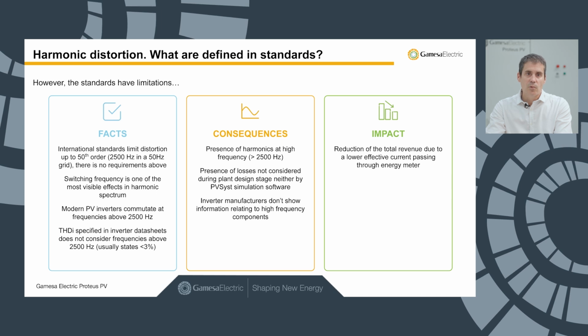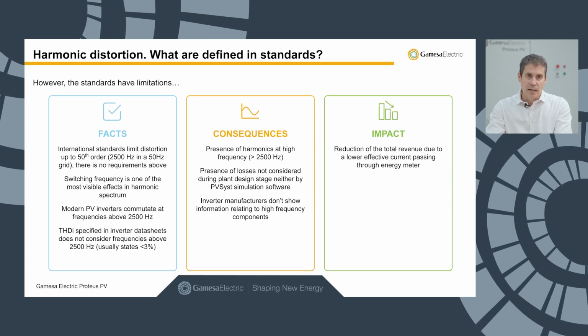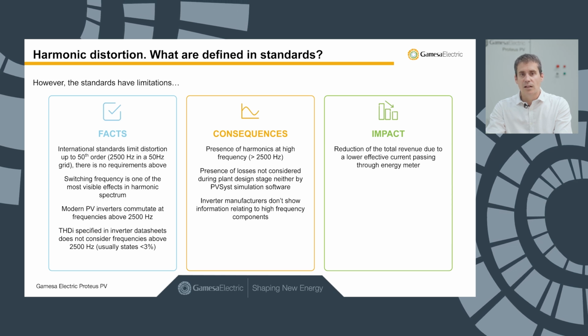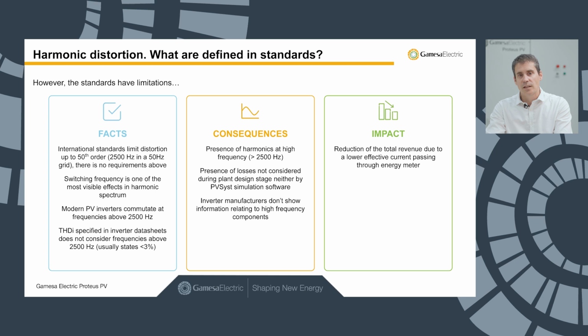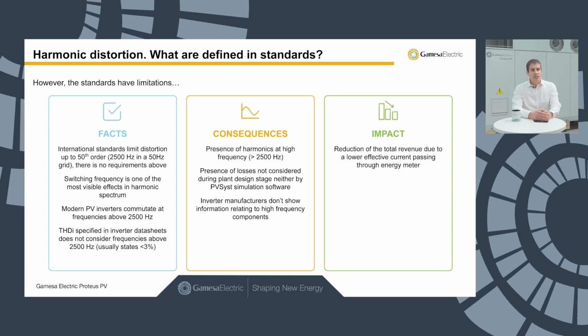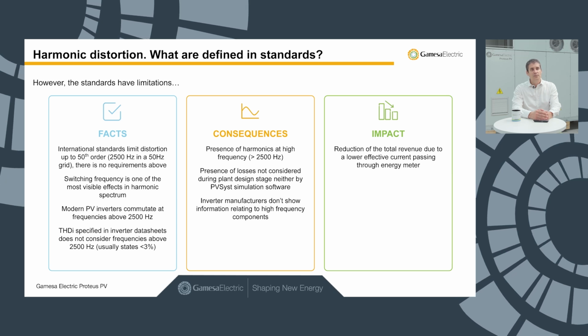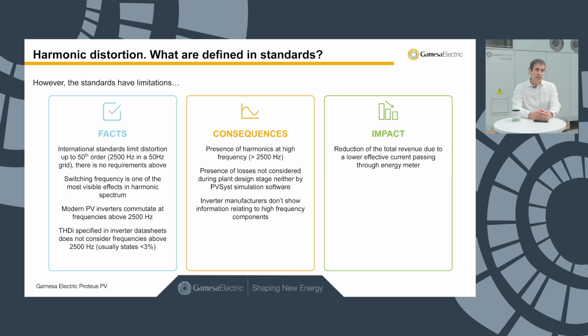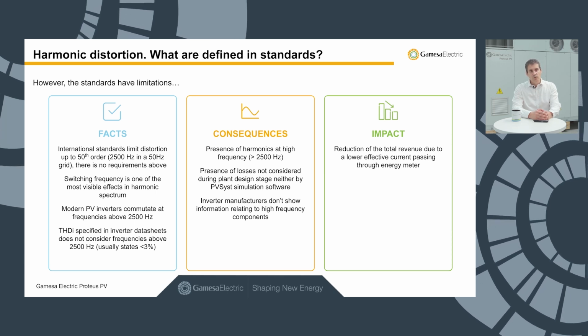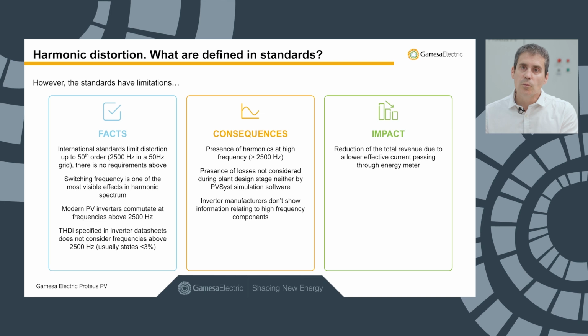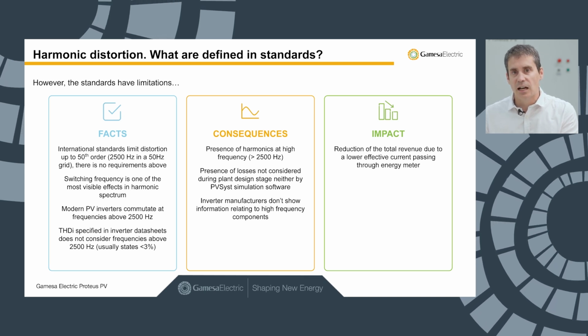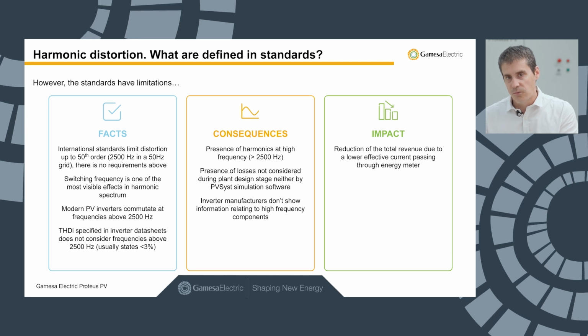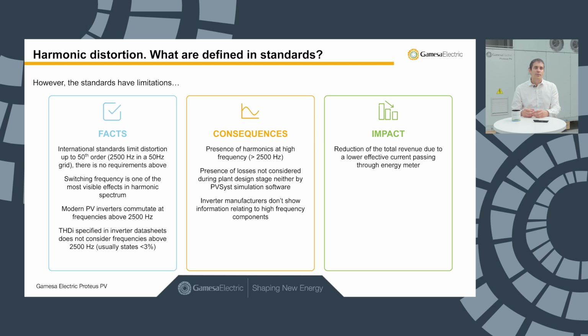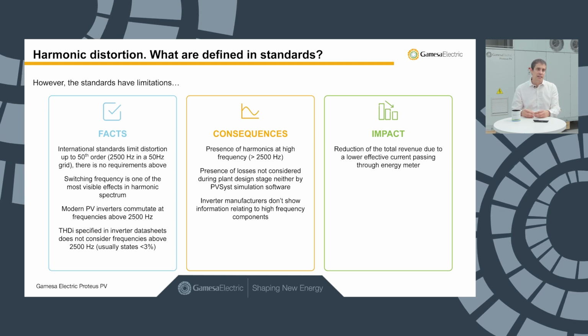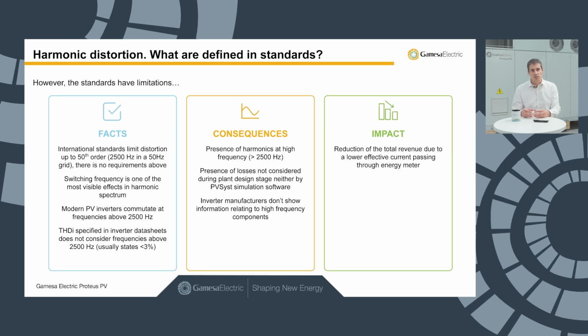The switching frequency is one of the most visible in the harmonic spectrum. But modern PV inverters commute at frequencies far above 2500 Hz. The THDI specified in the inverter datasheet does not consider frequencies above 2500 Hz, and usually they state THDI below 3%. What are the consequences of this? It could mean that we have a big presence of harmonics at frequencies beyond this 2500 Hz. The presence of losses is not considered during the plant design, neither by PVSyst's simulation software.